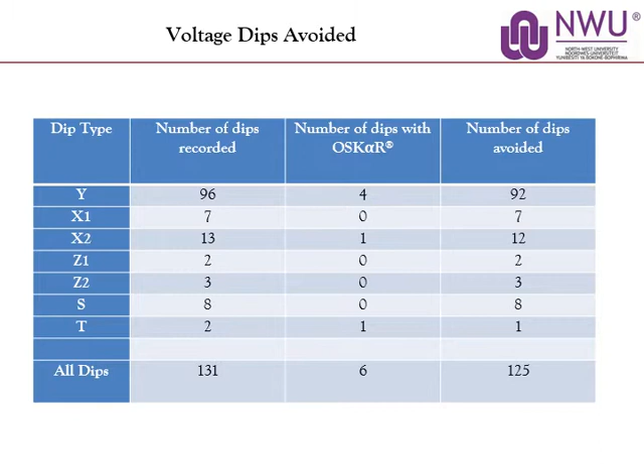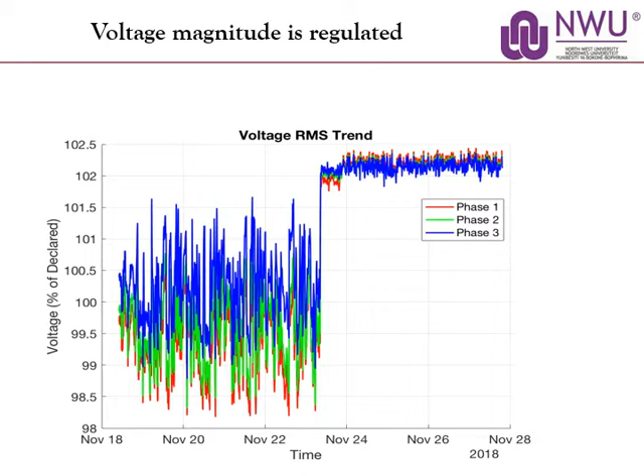But look what it is doing with voltage. This is in South Africa, where this German equipment is already working. Now, this voltage was not bad—zoomed in, you can see voltage changing from 98 to nearly 102%. This is not bad over a period of time. But look, the moment OSKaR kicks in, the load sees 1 per unit voltage all of the time, per phase. So you could have expected what happens with voltage unbalance—it's gone. Nothing remains.